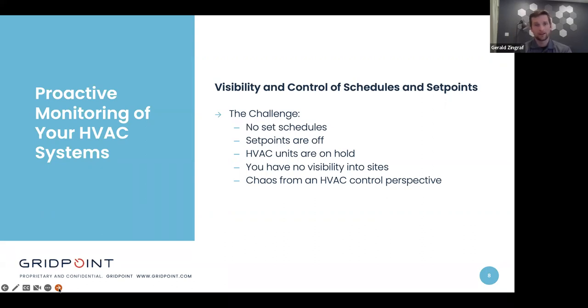My experience has been a little bit higher than that whenever I go out there and see these sites. So having thermostats set to permanent hold, having some thermostats set to heat while others are set to cool or auto, having the timestamps be off from thermostats. I just actually came back from a trip up in Boston a week ago, and timestamps were off by 7-8 hours in a handful of the sites that I went to.